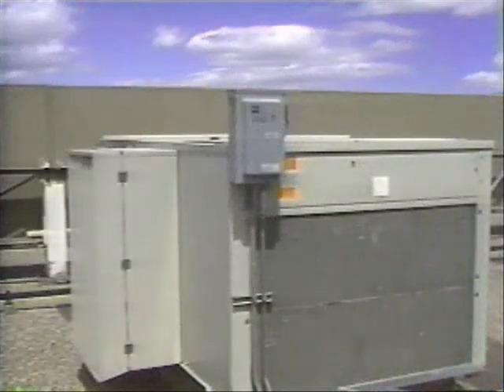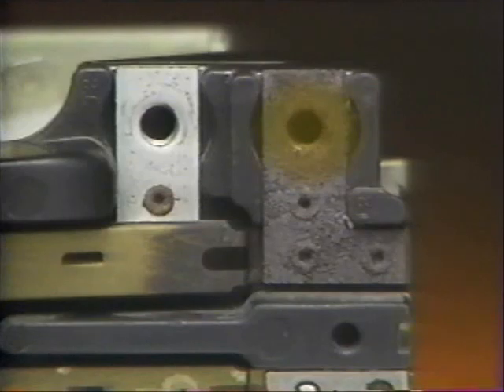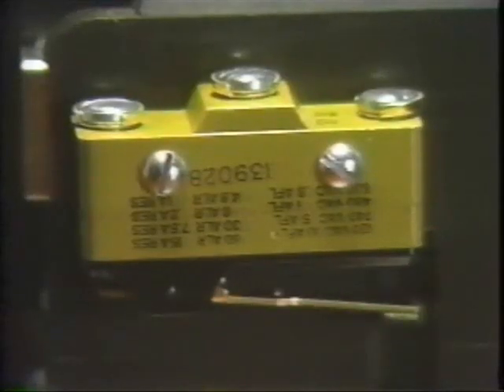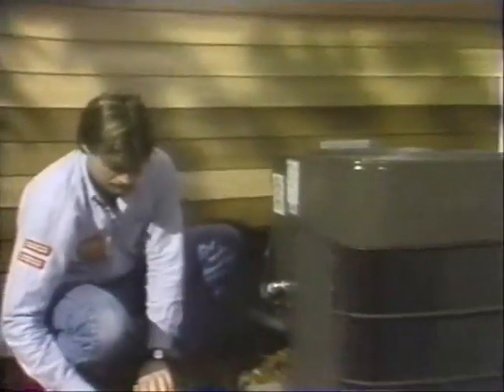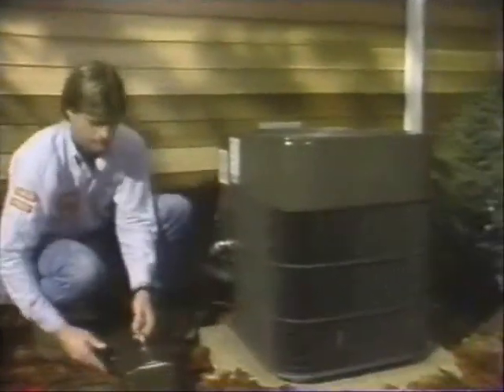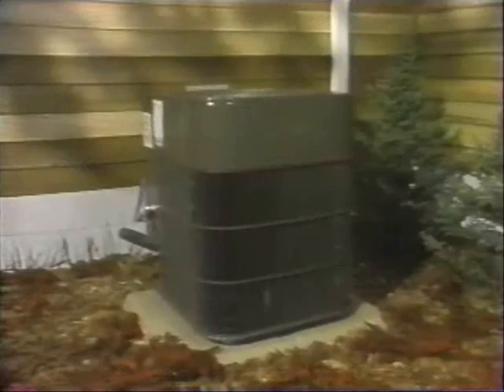If the contactor is located on the roof or another outside location, inspect the contactor to ensure that rusted and corroded terminals are not causing problems. If the contactor has an auxiliary switch, inspect it to ensure proper operation. The principles involved in air conditioning control are quite simple, and if you have a good understanding of these principles, you're well on your way to being able to handle any troubleshooting jobs that you encounter.